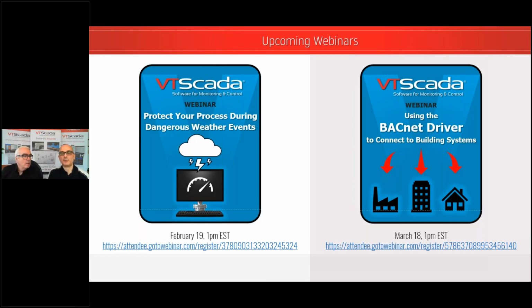The way redundancy usually works with VTScada, I think always works, is that every installation of VTScada has all the features built into it. So you don't have a separate historian, it's all one thing. Therefore, if you have two servers and you've got an application running on server A, then from server B, from VTScada, you can do what we call a get from workstation, where you reach across and pull in that application. Then you simply set your failover list, your server list, so that you know which one's the primary and which ones are the failover. You can add as many redundant servers to that list as you want. We don't limit the number of servers for failover with redundancy. You can have as many as you have VTScada licenses.